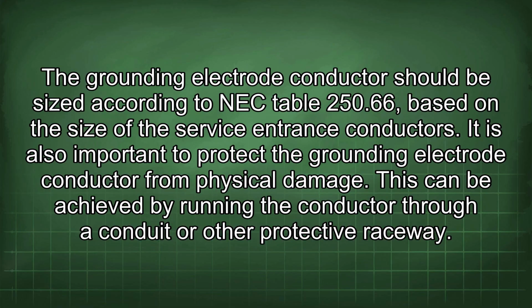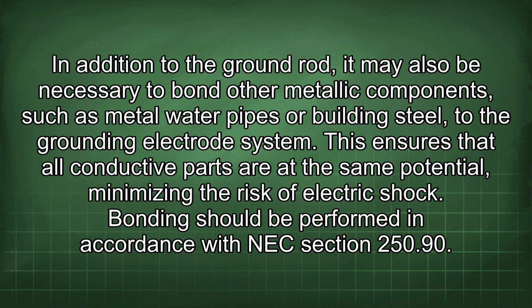It is also important to protect the grounding electrode conductor from physical damage. This can be achieved by running the conductor through a conduit or other protective raceway. In addition to the ground rod, it may also be necessary to bond other metallic components, such as metal water pipes or building steel, to the grounding electrode system. This ensures that all conductive parts are at the same potential, minimizing the risk of electric shock. Bonding should be performed in accordance with NEC section 250.90.